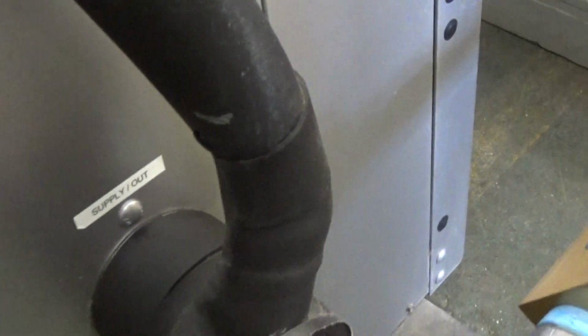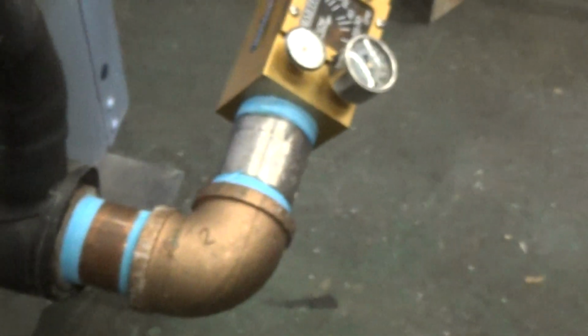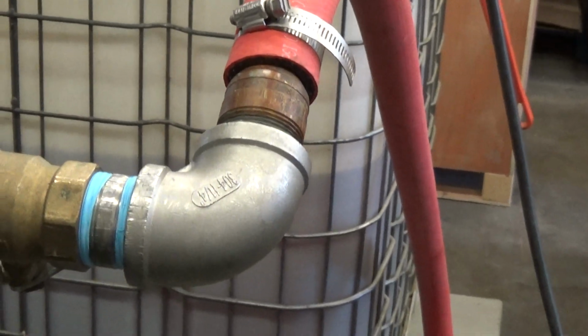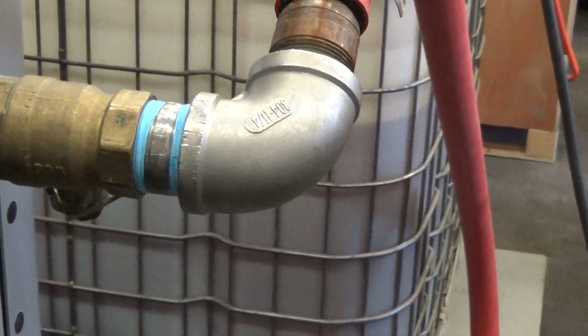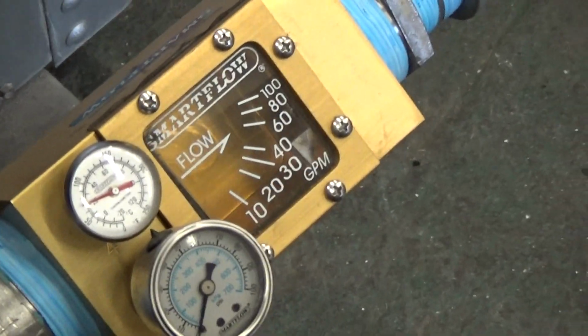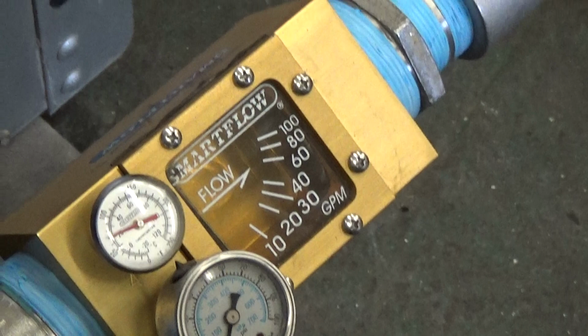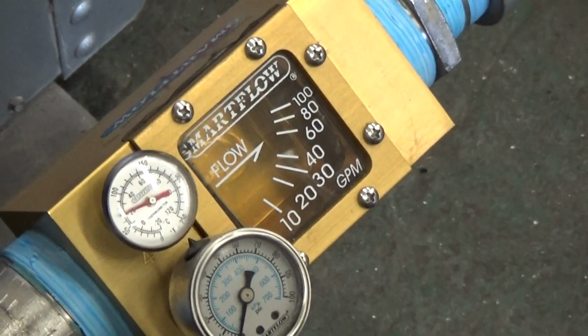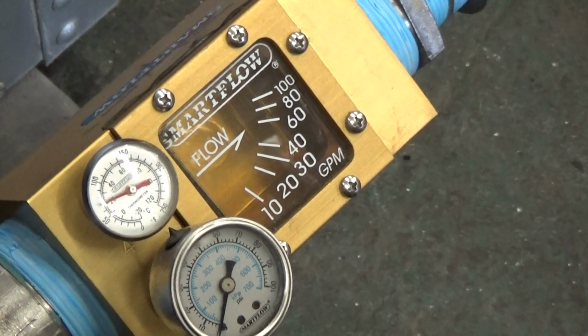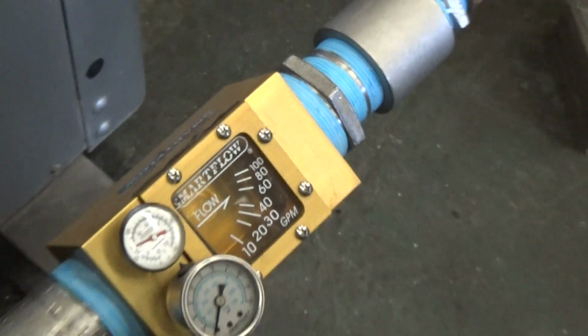That's the temperature sensor there. The output comes here, and we have it labeled supply out. And for our testing, we just have a short hose here where the chiller is just chilling itself with a tank of water. When we do run the unit, we put a flow meter on here. Ideally, you want to see about 2.5, give or take, 2.5 GPM per ton. So that equates to about 50 GPM for something like this. That'll give you the best cooling.